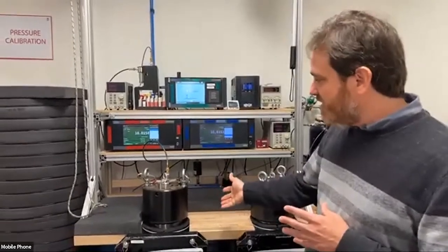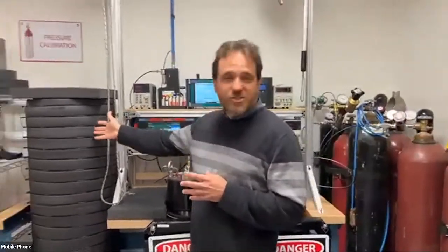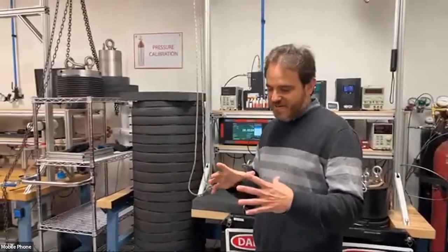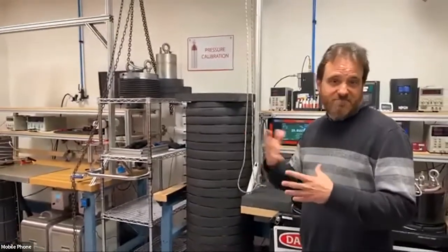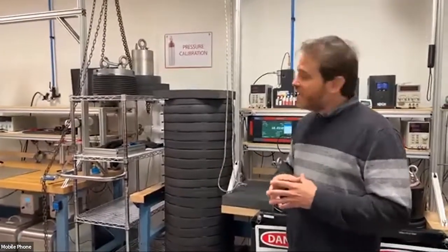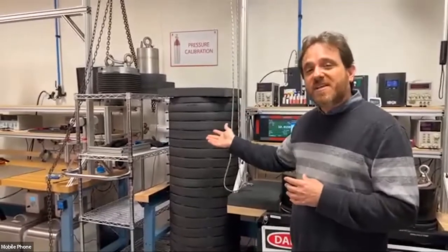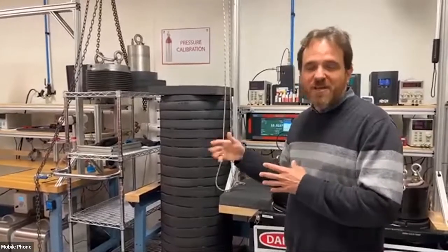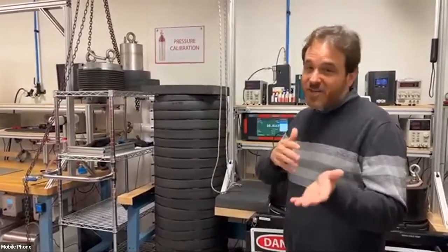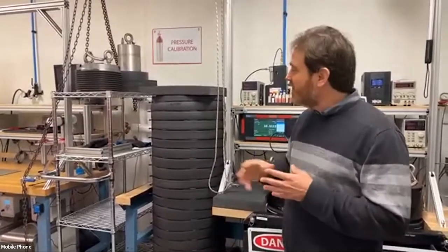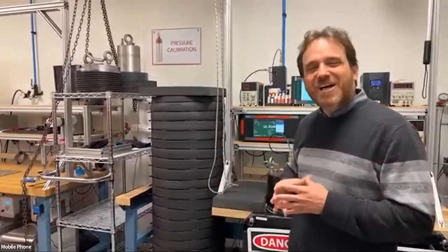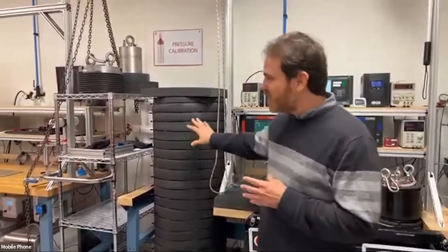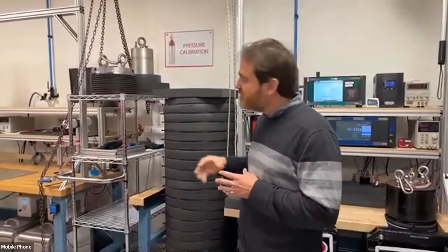So yeah, we have these two tanks. We actually have a larger diameter tank in order to fit larger units, such as OEM floats. We also do some pressure testing, which is what we call bladder testing, where we confirm pressure dependency on the conductivity of the cell, which I believe might be a source for another webinar, but I just wanted to show you guys what this tank is used for.